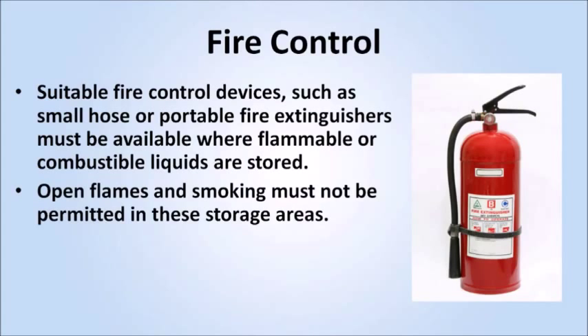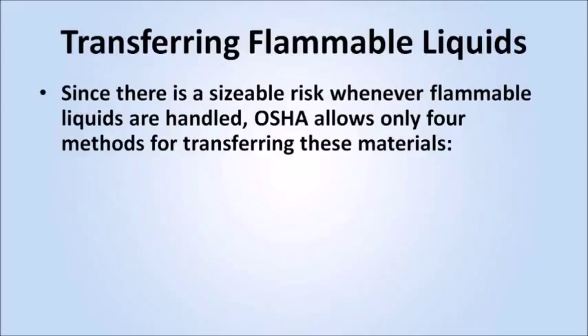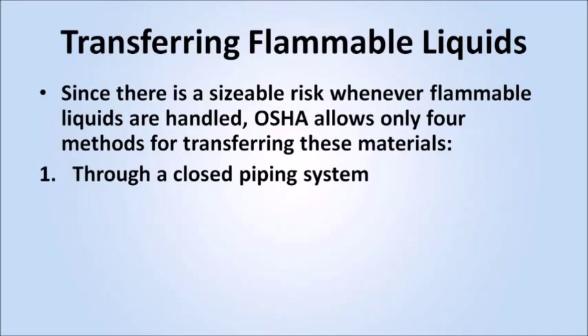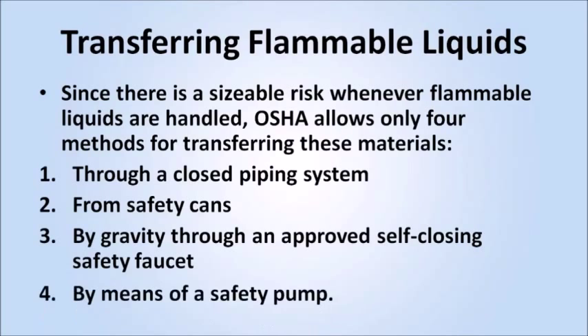Open flames and smoking must not be permitted in these storage areas. Materials which react with water must not be stored in the same room with flammable or combustible liquids. Since there is a sizable risk whenever flammable liquids are handled, OSHA allows only four methods for transferring these materials: through a closed piping system, from safety cans, by gravity through an approved self-closing safety faucet, or by means of a safety pump.